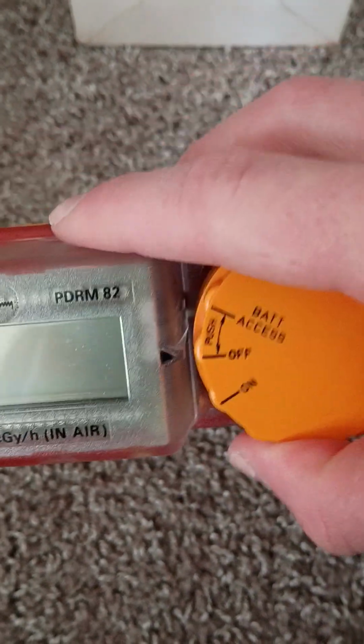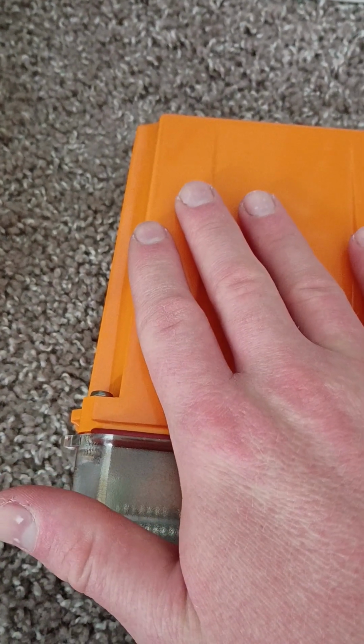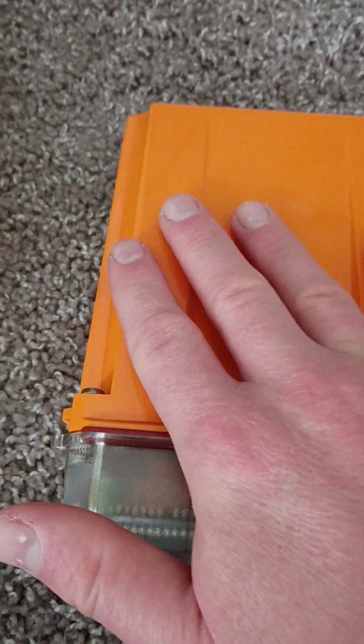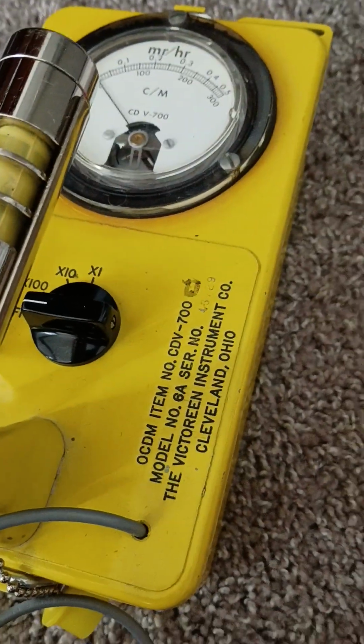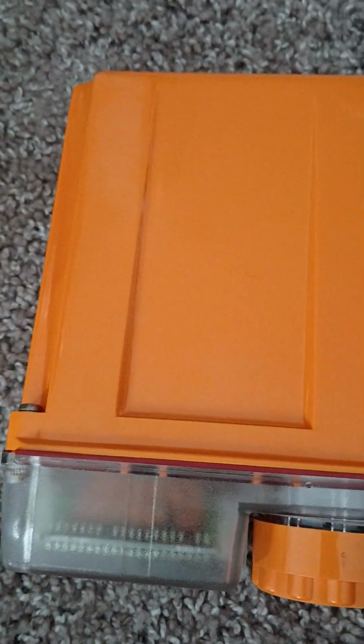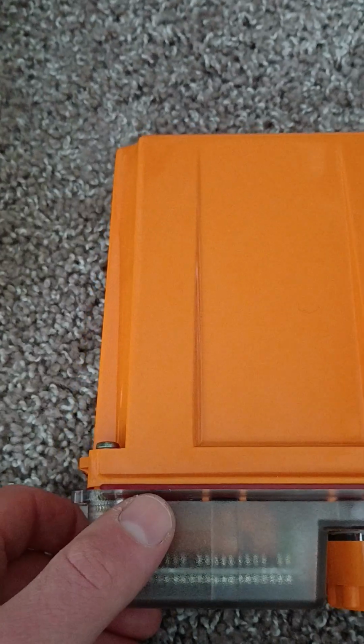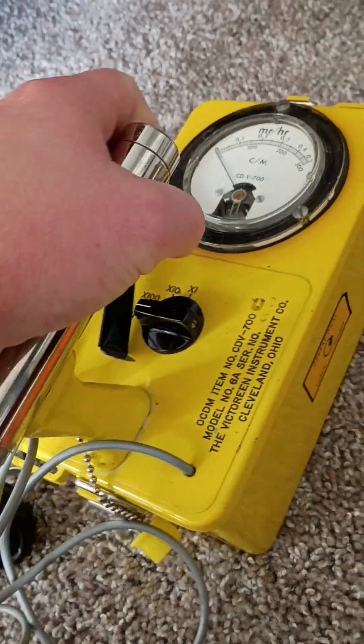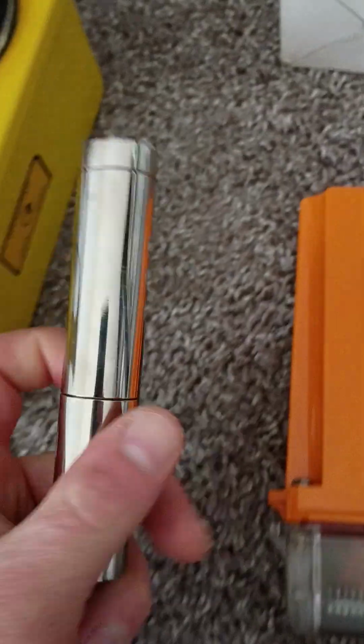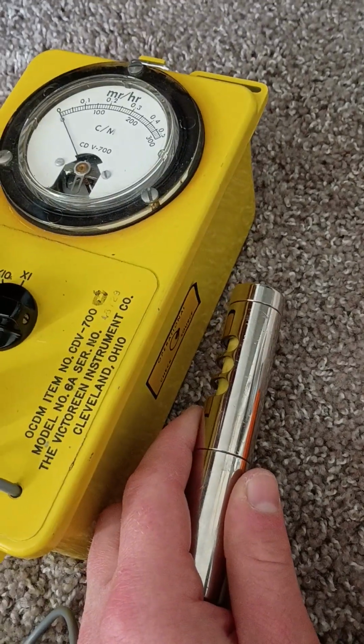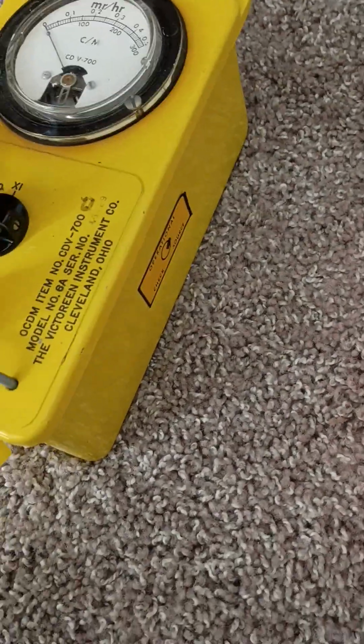Now, something that I was waiting until now to discuss, which I've released a video on in the past, is that inside the electronics there is actually an internal check source that is part of the physical boot up process of the device. Now, most meters, and for those that don't know, a check source is a small source of radioactivity that allows you to check the functionality of your device, calibrate, etc. Now, something like this has a check source mounted to the side on this CDV700. It is a piece of depleted uranium, and what you would normally do on most devices is you would take your probe and you would wave it near this, and the clicking that would result would tell you that your device is in fact functioning.